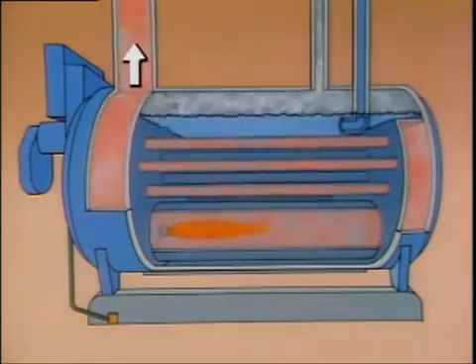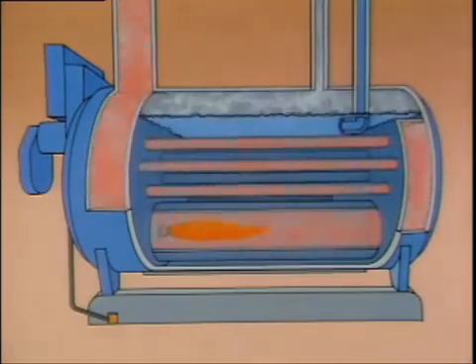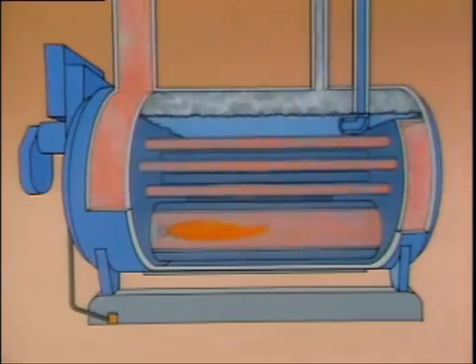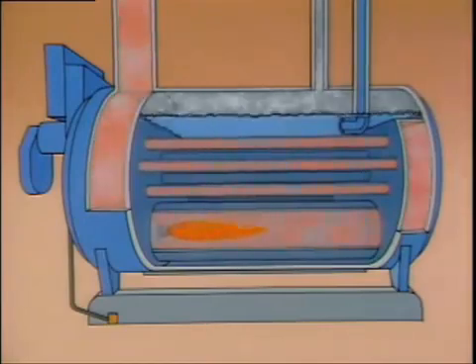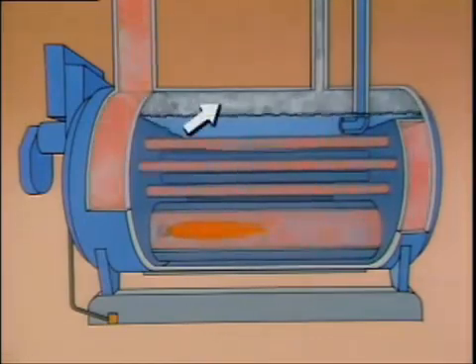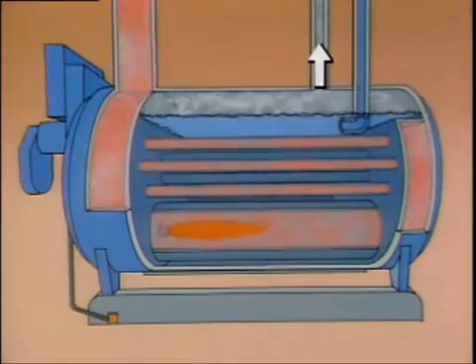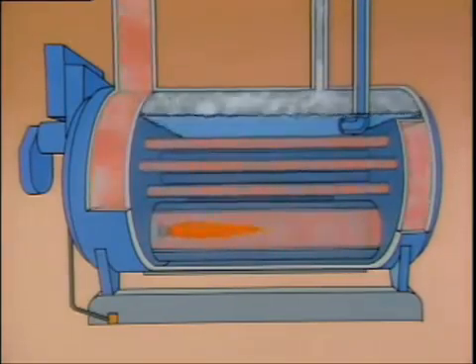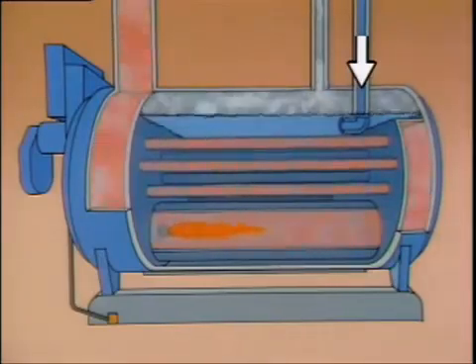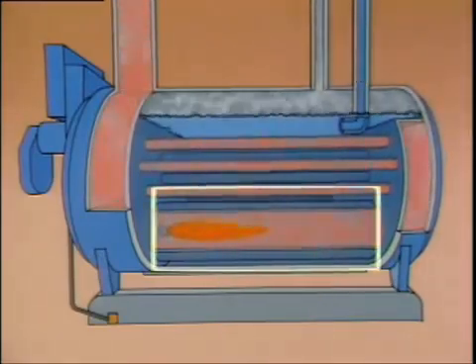The combustion gases flow out of the boiler after the passes. As the water in the boiler is heated, some of it turns to steam. The steam-water mixture is lighter than the cooler water in the boiler, so it tends to rise, and steam collects above the water level, then flows through the outlet and into the plant. The feed water, which is cooler and heavier than the steam-water mixture, flows to the bottom of the boiler, is heated in the combustion area, and the cycle continues.